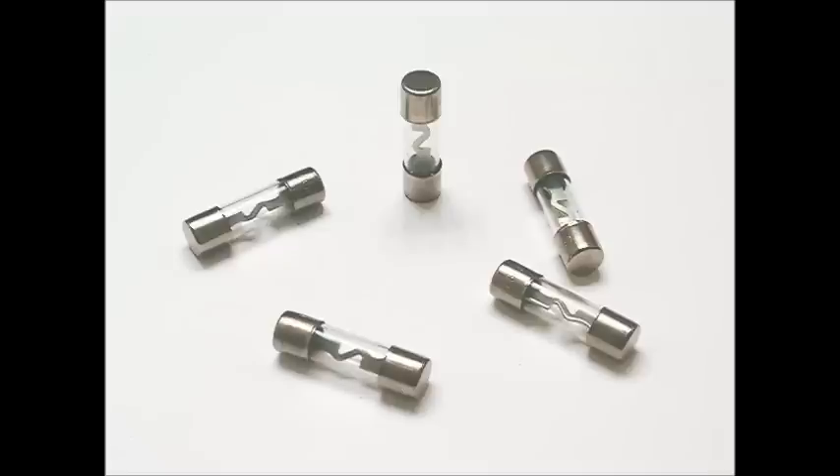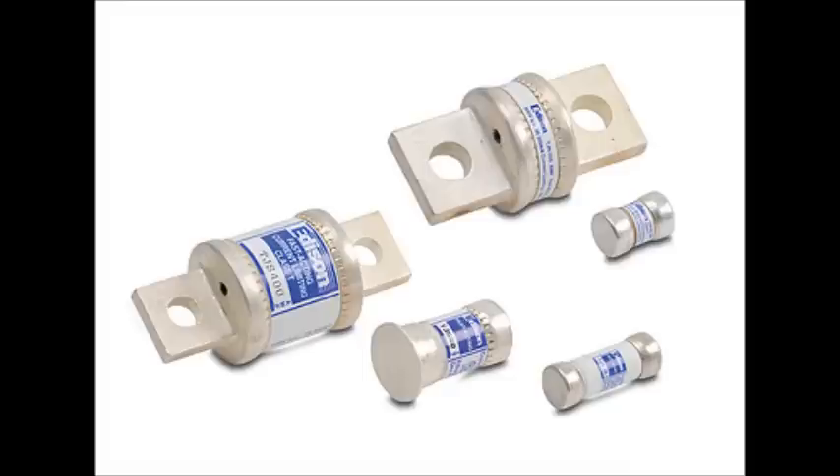The tortured path — occasionally if you look at a fuse, you ever see a fuse that almost looks like a lightning bolt, where the path of the fuse is going left, right? That is what's called a tortured path. Other times you'll see a fuse that's huge — almost the size of a baseball — and what those are: they've got a straight-through path, but the path is filled with sand. So as the fuse itself is burning away, sand fills the area and displaces the plasma gas.